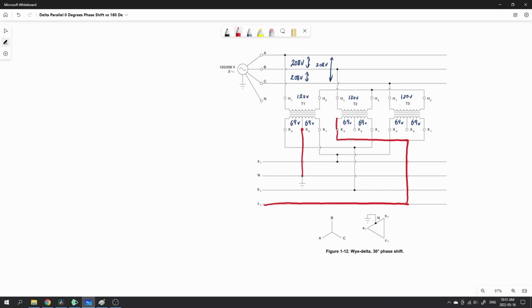Through one of these windings, so it looks like we'd go through both of these guys, pick up 138 volts. Then we come over here, pick up 69 volts before going back to the ground there. So it looks like one of the paths from C to that neutral would be like this, right? Picking up the 138 between these guys, and then picking up 69 volts from the first transformer there. So with this one, we have the 69 volts, which is on transformer 1, so 69 volts at 0 degrees.